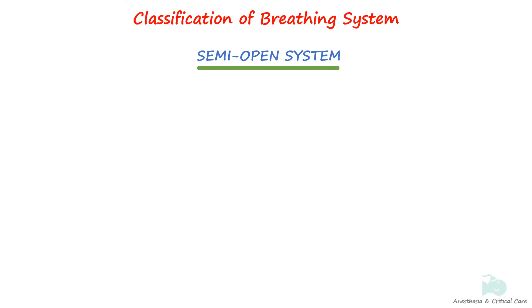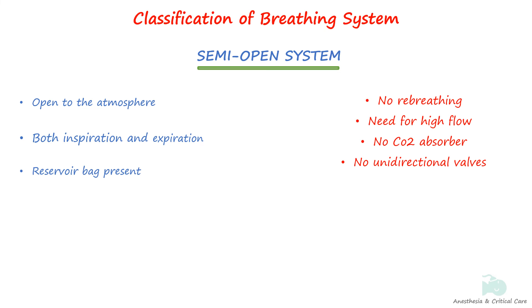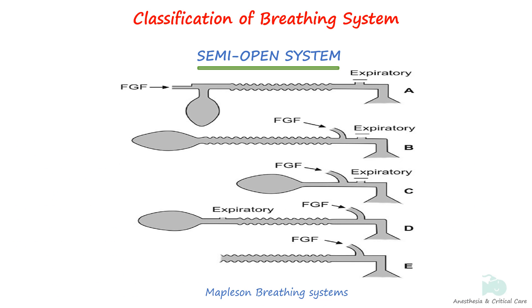In a semi-open system, the patient's respiratory system is open to the atmosphere both during inspiration and expiration through a reservoir and breathing tubes that are open to the atmosphere. The atmospheric air either carries or dilutes the anesthetic agents. Semi-open breathing systems have a reservoir breathing bag, no functional re-breathing of exhaled gases, and need high fresh gas flows to prevent inhalation of exhaled carbon dioxide. There is no neutralization of carbon dioxide and no unidirectional valves. These include Mapleson breathing systems, which will be discussed in detail in the next video.